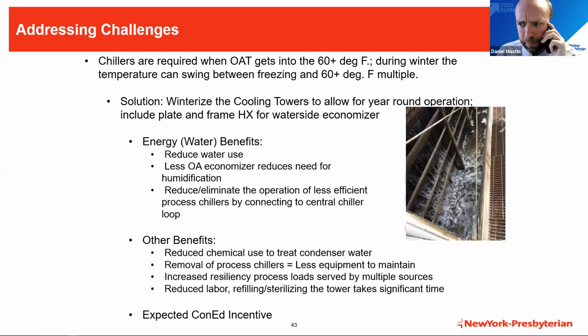One project where we were able to stack multiple values is winterizing a couple of our cooling towers. Right now, anytime temperatures drop below freezing outdoors, we have to drain the cooling towers below the roof line and shut down the central chiller plant. This requires multiple process chillers for imaging equipment, pharmacies, and other critical areas throughout the campus, so we have process cooling all over the place that's not on the central plant. Once we winterize our cooling towers, we'll be able to operate the central plant year round.